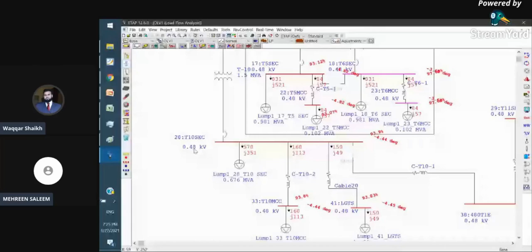We no longer need to worry about the voltage drops, because equipment functions in a healthy manner if it is given more than 95% of the rated voltage. So by changing the transformer taps, we are solving the problem of under voltage. But there are many other options, like introducing capacitor banks into the network, where the excess reactive power given by the capacitor banks will boost the voltage level. Another option is to shift the loads, because the more inductive loads are concentrated in one part of a network, the lower the voltages, especially away from the sources. By distributing the loads properly in the electrical network, we will have a much better voltage profile. But most of the time, a practical solution to achieve a voltage profile above 95% is to play with the transformer taps.